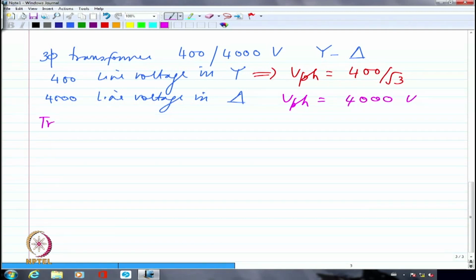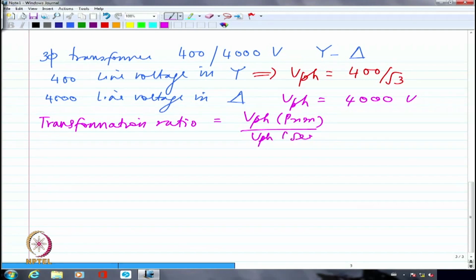So to calculate the transformation ratio for this transformer, I have to take V phase of primary divided by V phase of secondary, or vice versa — it doesn't matter. So I take this as 400 divided by root 3, divided by 4000. Even though the voltages are written as line voltages, when calculating the transformation ratio, I always take per phase values. Unless I take per phase, it is incorrect. So we generally look at per phase voltage ratios.